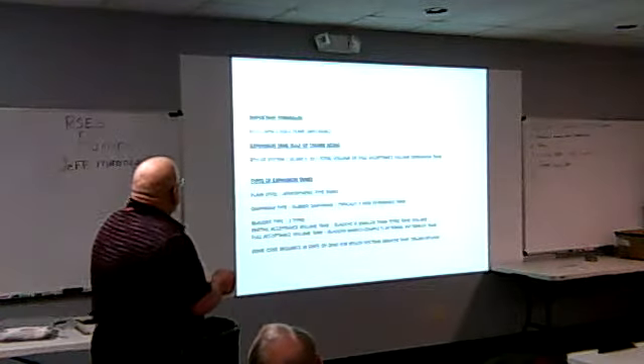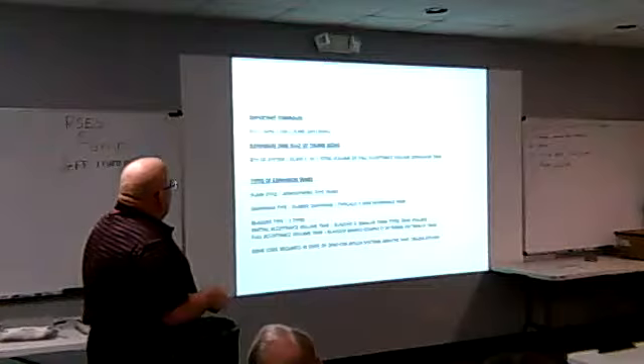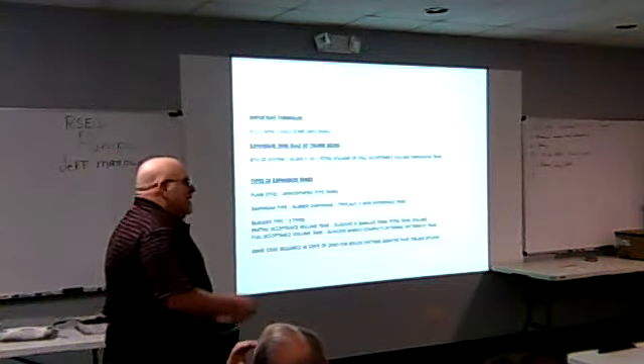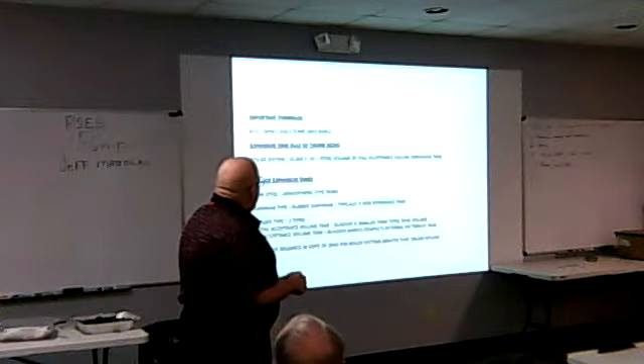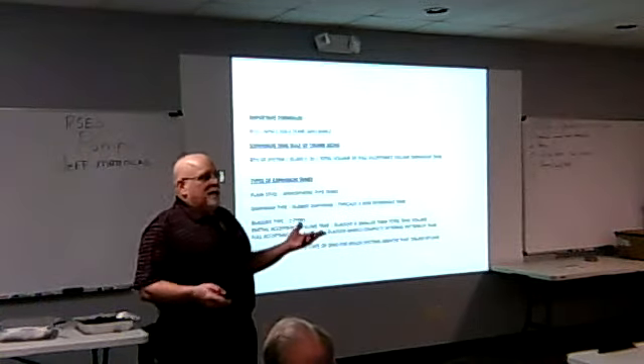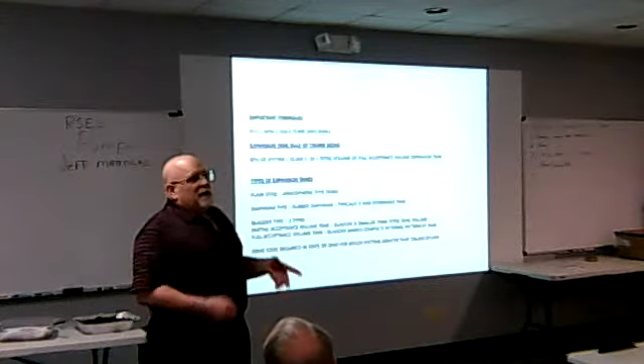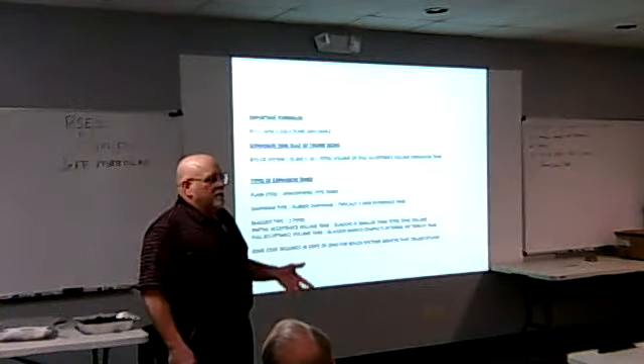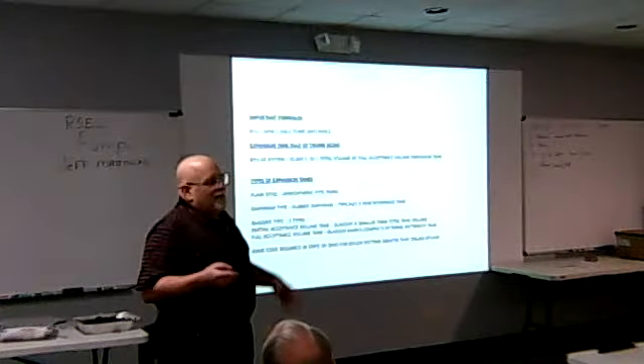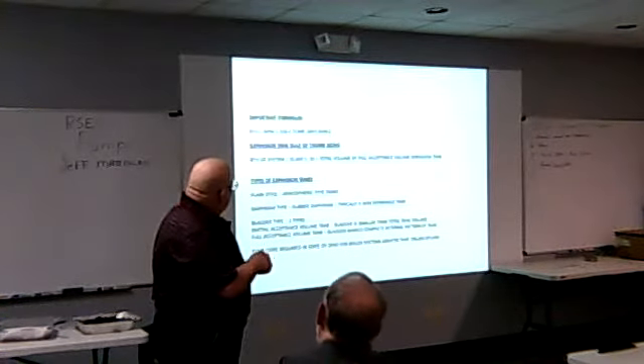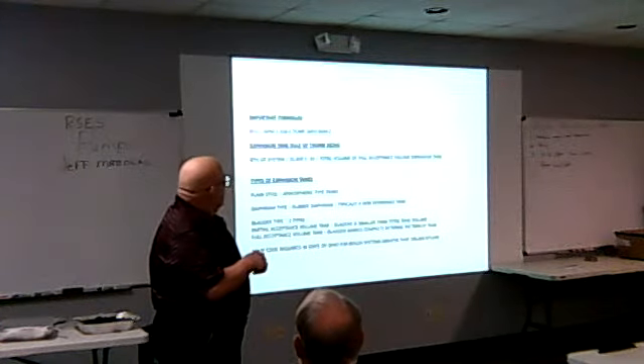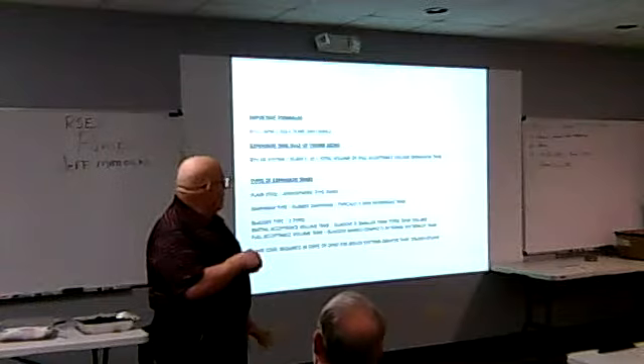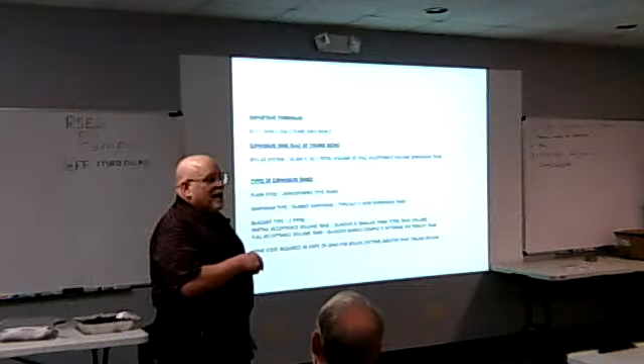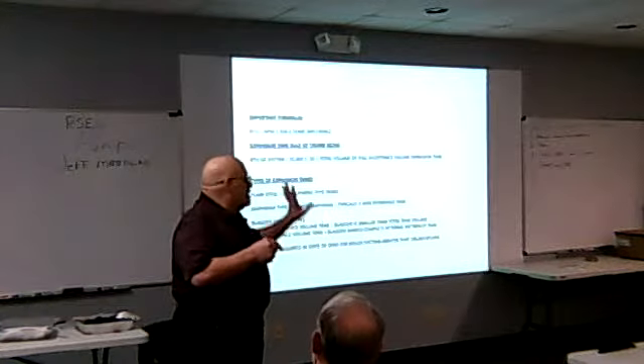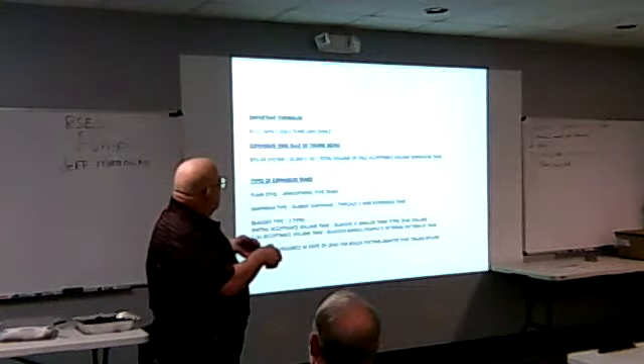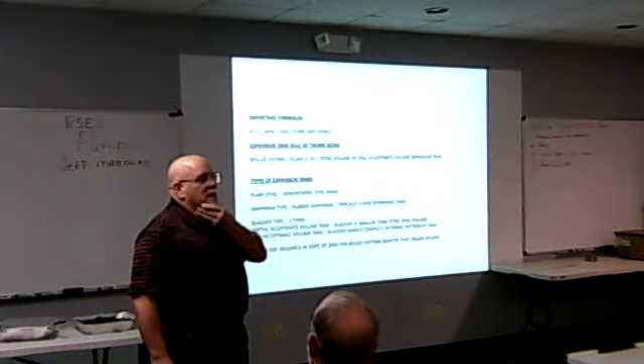Okay, this is a rule of thumb we use a lot of times. People will call us and say, hey, I need a new expansion tank, and all I have is a plain steel tank. I can estimate the volume in that plain steel tank. Expansion tanks are really sized by system volume, but this rule of thumb comes in very handy. If I have a boiler system, I take the BTUs of the boiler and divide by 15,000. If I have a 12 to 20 PSI fill system, that gives me the full acceptance of the tank. I can go into my chart. There are 2 different kinds of expansion tanks, we'll get to that in a minute. This is the full acceptance, and I can pick a tank, and I've never had one not be right.